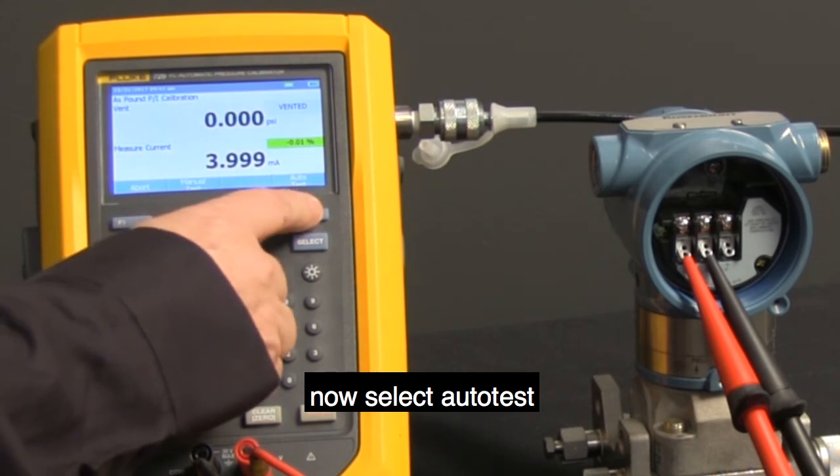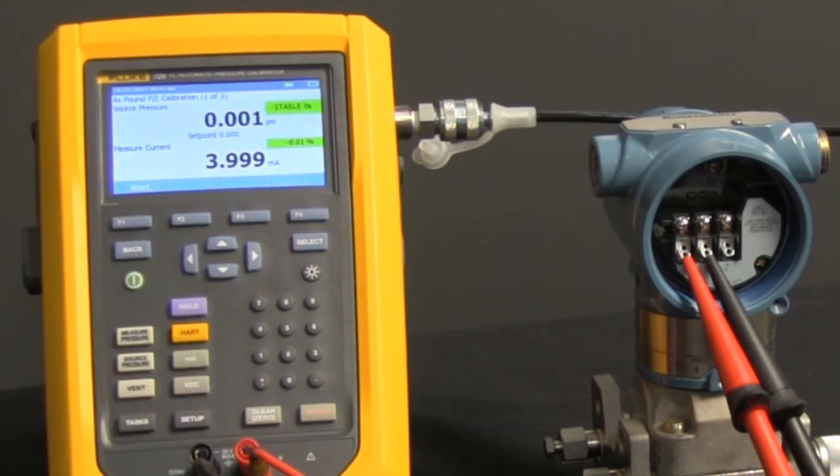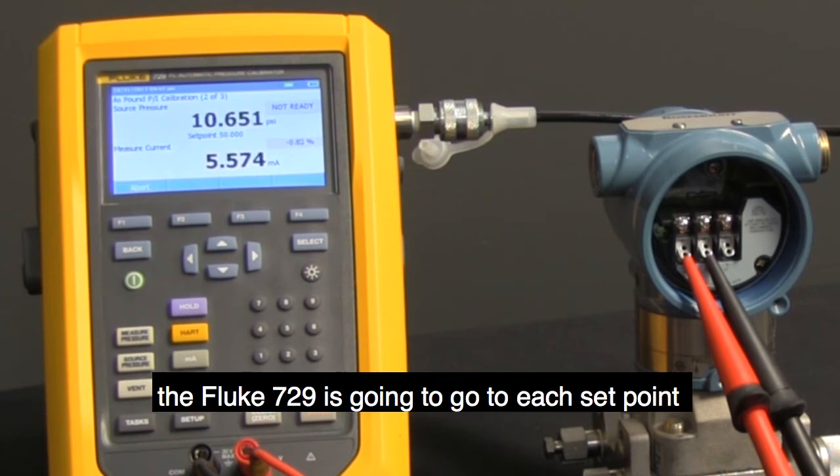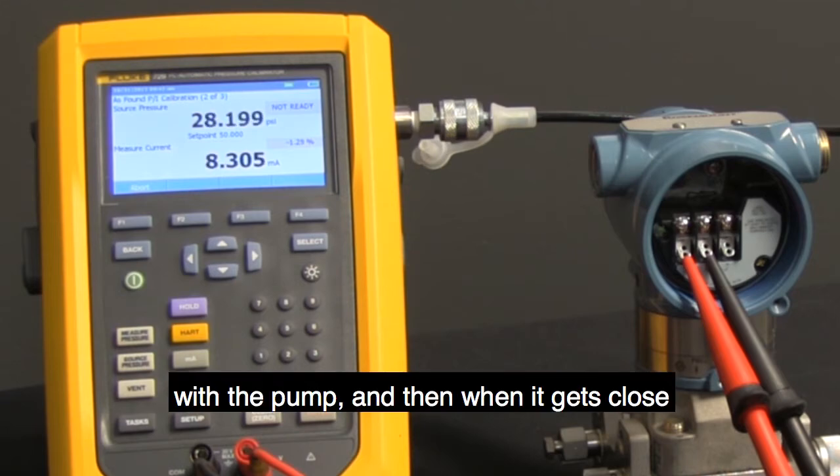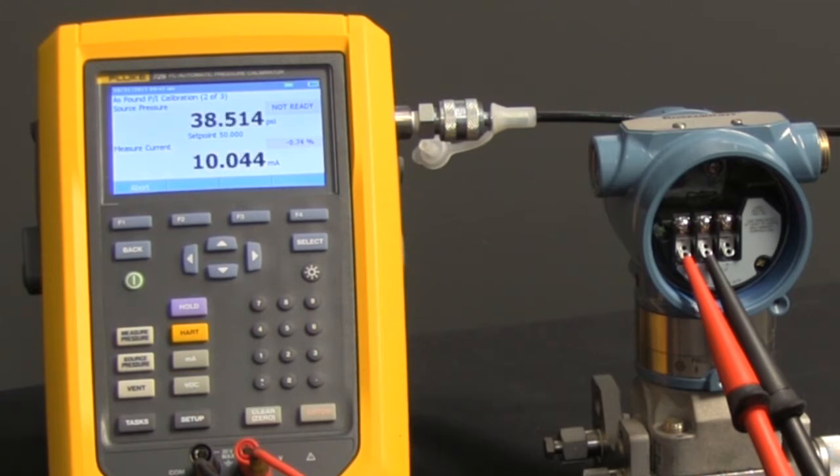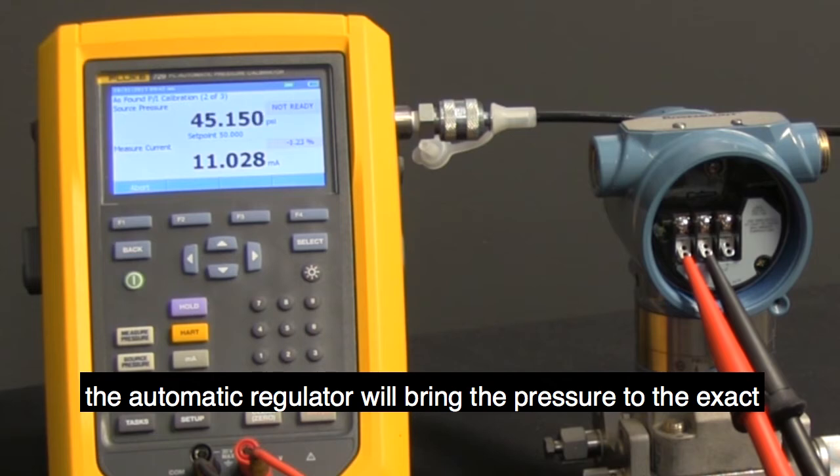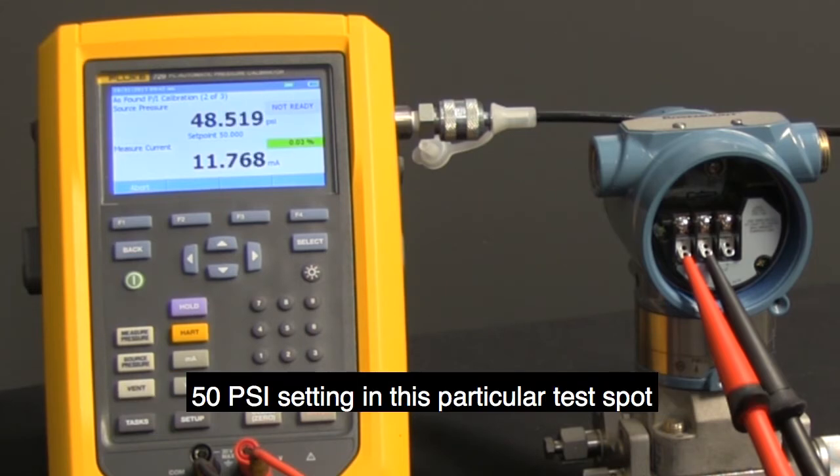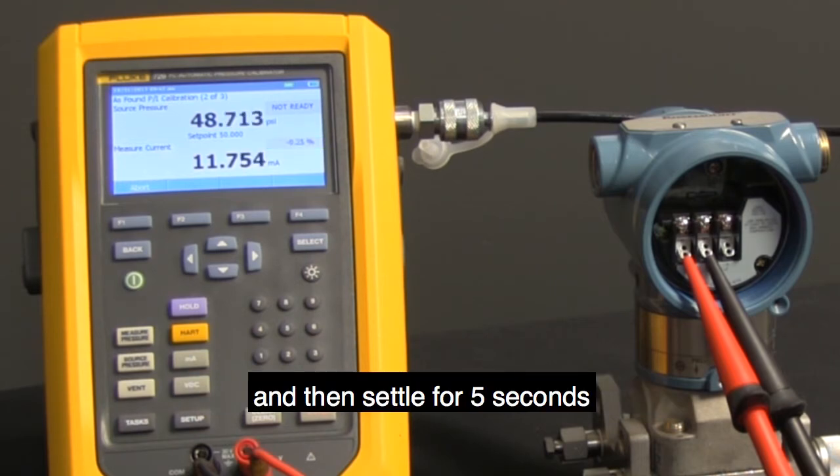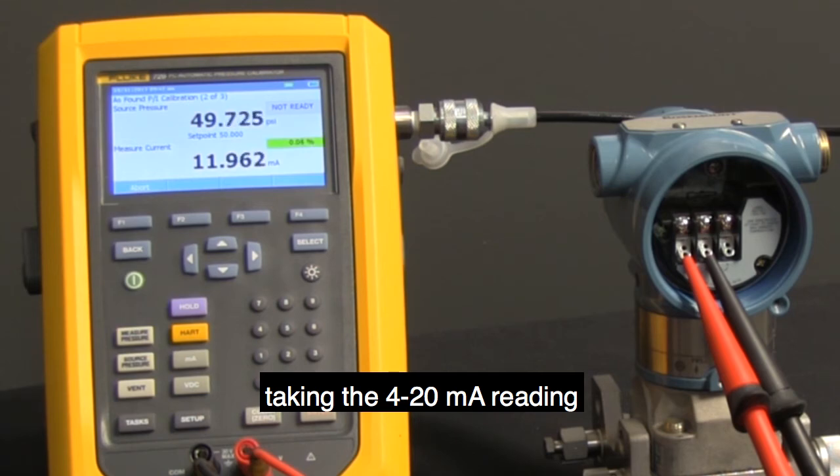Now, select Auto Test. The Fluke 729 is going to go to each set point with the pump, and then when it gets close, the automatic regulator will bring the pressure to the exact 50 PSI setting in this particular test spot, and then settle for 5 seconds, taking the 4 to 20 milliamp reading.